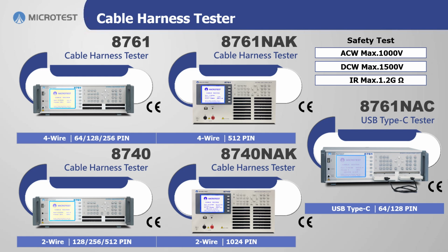Regarding withstand voltage output, AC can provide up to 1 kV, DC with a maximum of 1500 volt, and the highest insulation impedance measurable is 1.2 GΩ. For test points, the 4-wire measurement can handle up to 512 points, while the 2-wire measurement can handle up to 1024 test points.